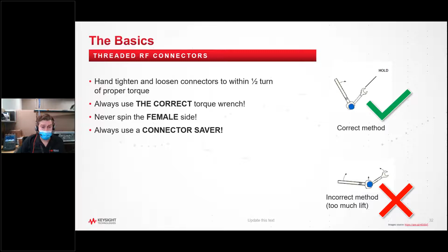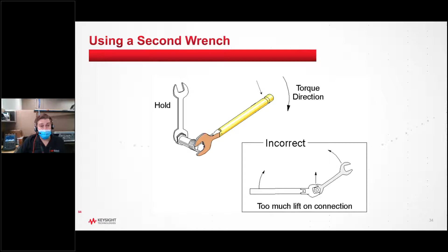If you have to hold the other side, you use a second wrench and just keep it static and don't move it. And then you rotate the torque wrench until it breaks. Don't turn both wrenches because that can apply some lateral force on the center pin. Like I said, grab it here and push until it's just broken. You don't need to go all the way around. It's no longer a calibrated measurement if you do that.